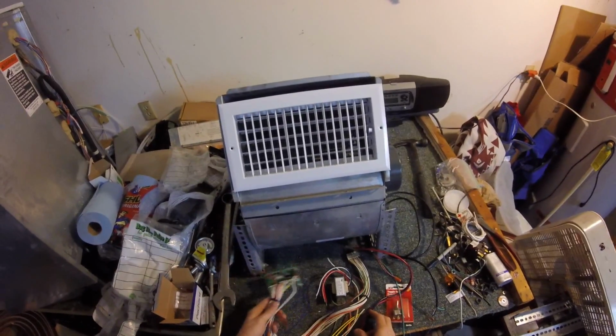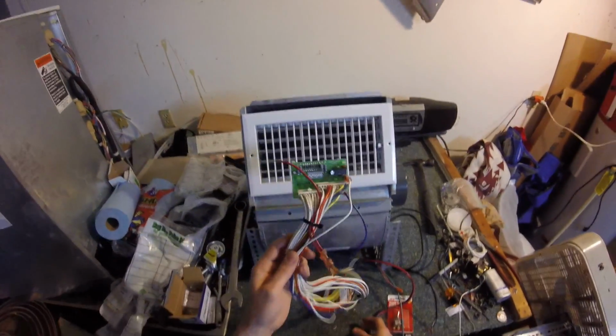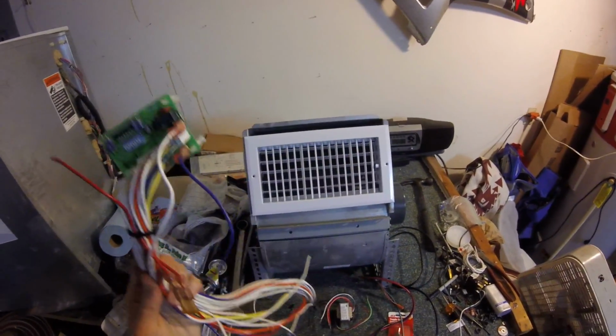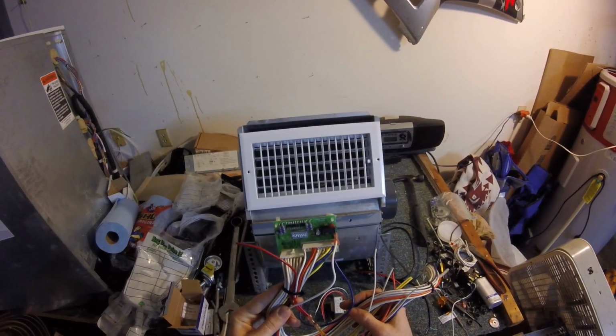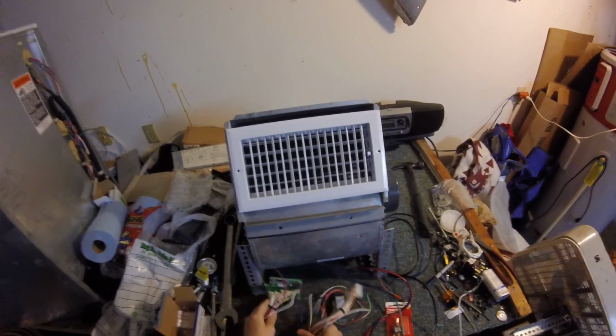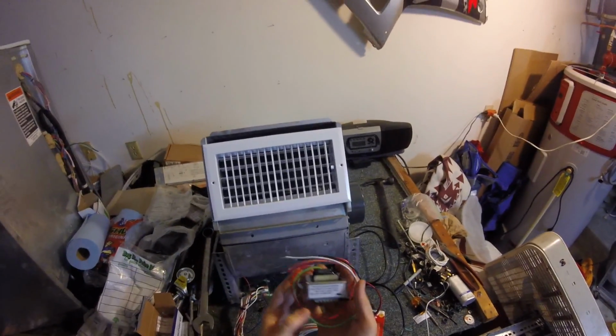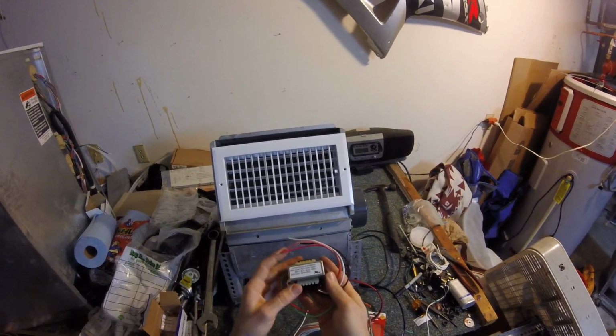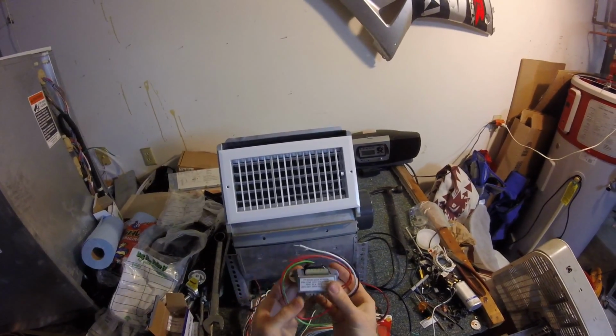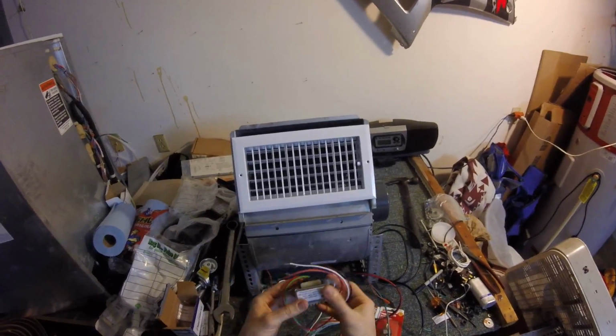Wiring materials that we need for this job: here is the low voltage circuit board off the old air handler. We're going to need a little transformer, 115 volt, 20 VA, really small and compact, because we don't need very much.